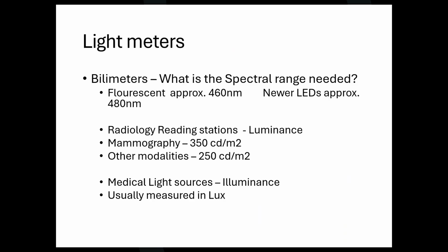So mammography, those reading screens have to be brighter than a typical X-ray. Look at what they're trying to find. They're trying to find that most minute detail, and you'll see them. You walk up and they're sitting in front of the screen with a magnifying glass, looking over it. So that is a higher standard that has to be met for mammography reading over just the one they're using to see, did I break my arm. Okay, illuminance, different meter, typically so many lux. That's just for light sources, things like that.